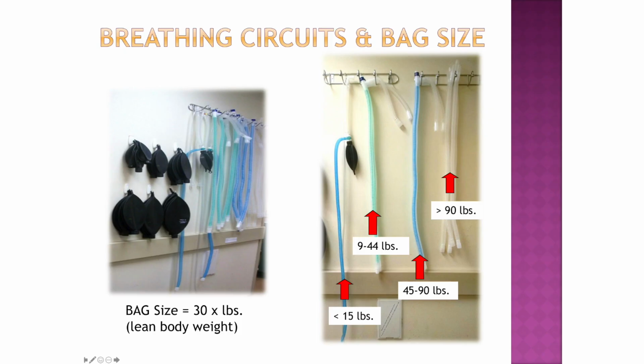But in general, the really, really big hoses, these are for 90 pounds or greater. When you see the blue F circuit, these are for 45 to 90 pounds. These teal ones here are about 15 to 44 pounds. And then we use these non-rebreathers for basically if the animal's breath size is too small to move the flutter valves. That's when push comes to shove and you must use one of these non-rebreathers.